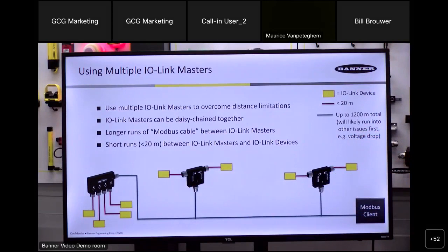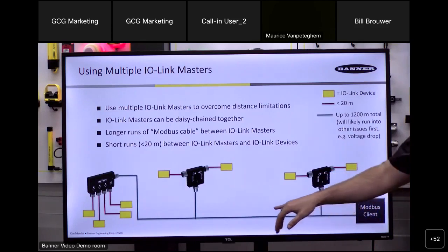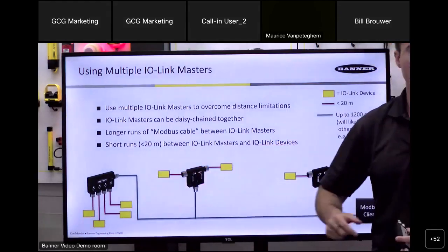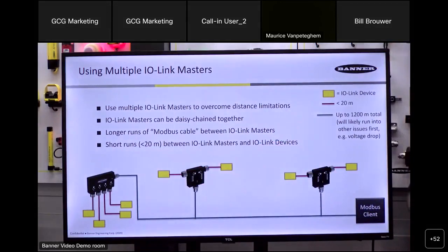And what are some of those distance limitations? Well, with IO-Link masters, you're limited to 20 meters between your IO-Link device and your IO-Link master. However, with Modbus, you could run up to 1,200 meters of wiring. So it allows you to come up with a solution that's really the best of both worlds.